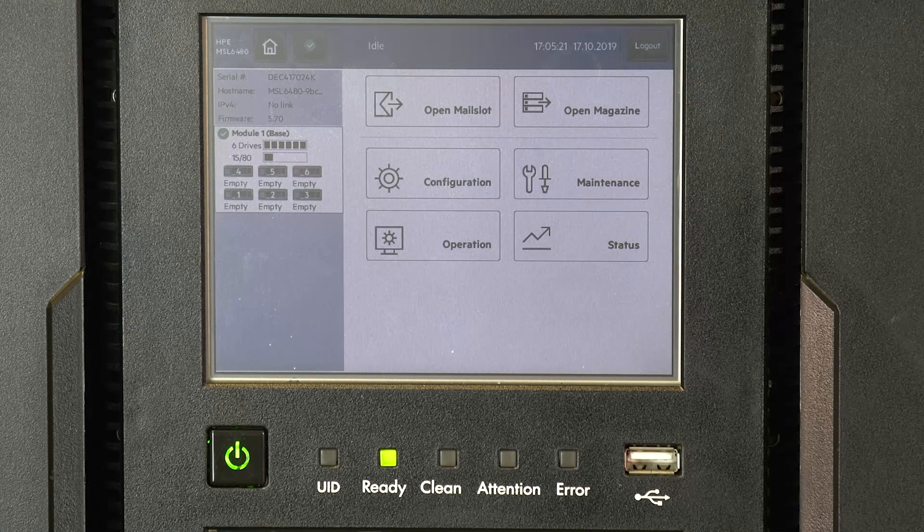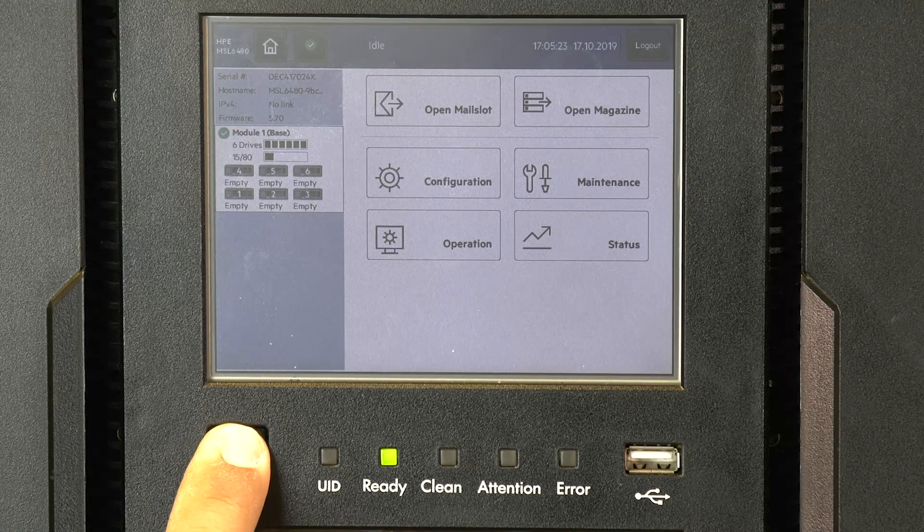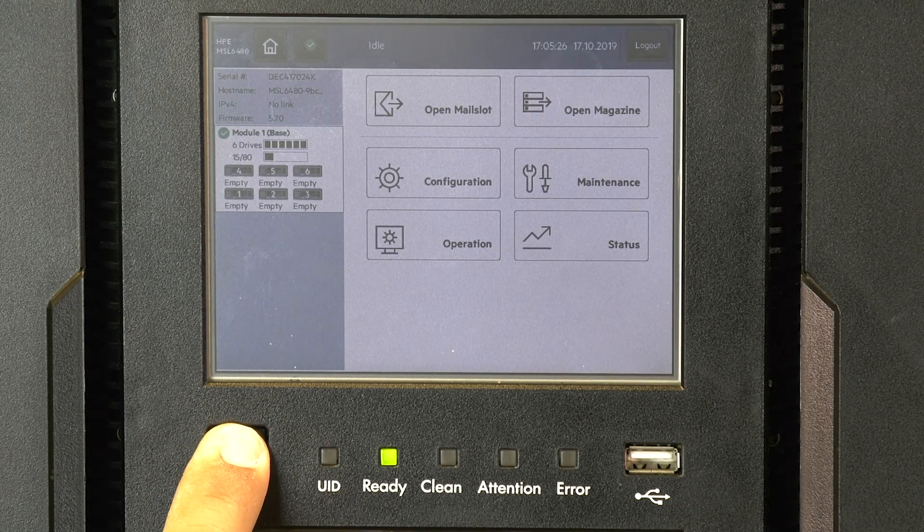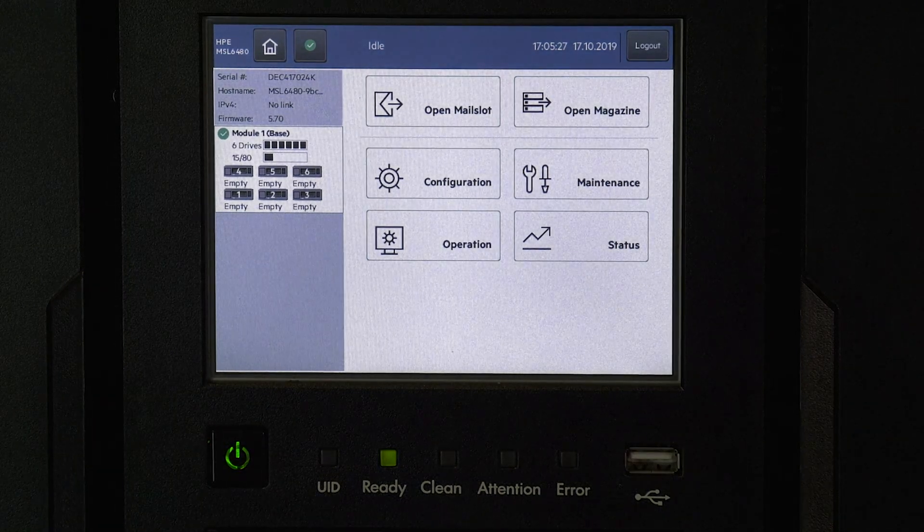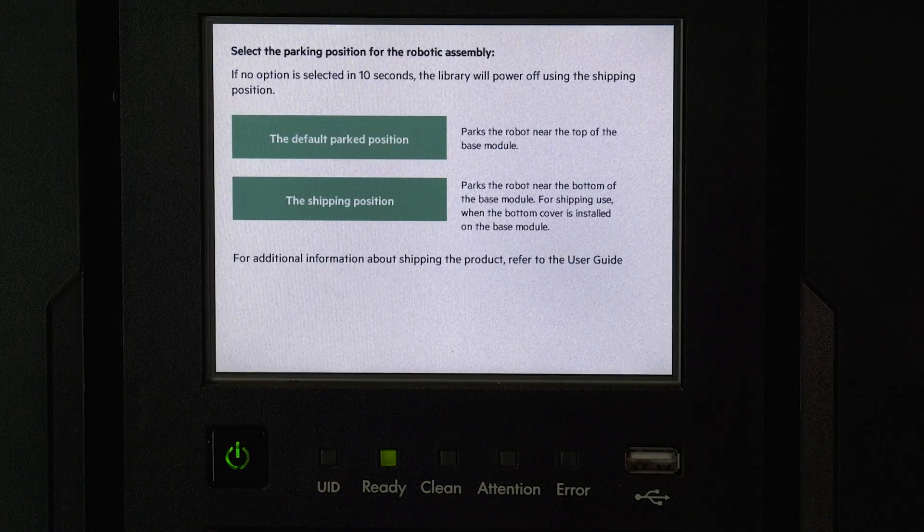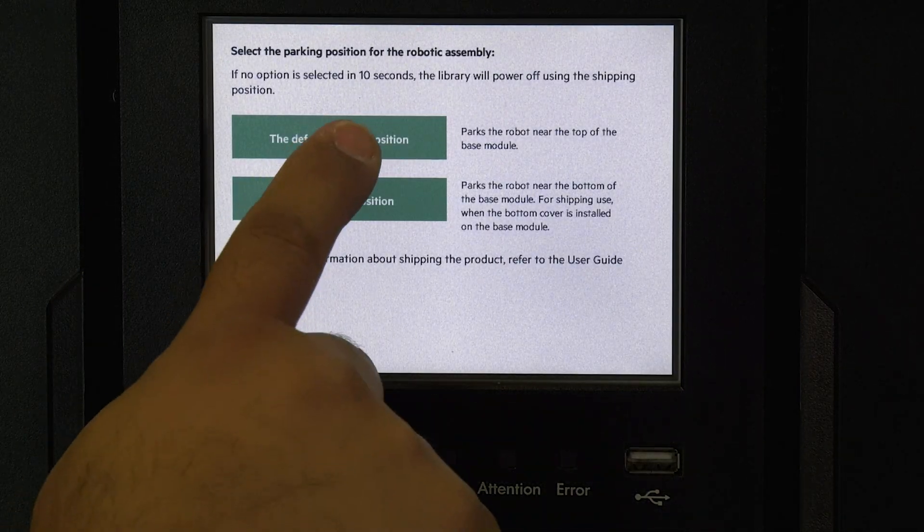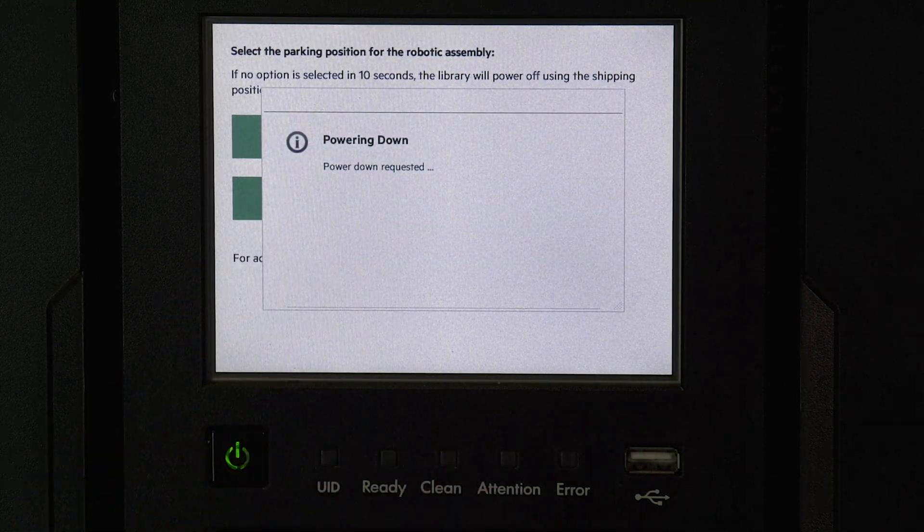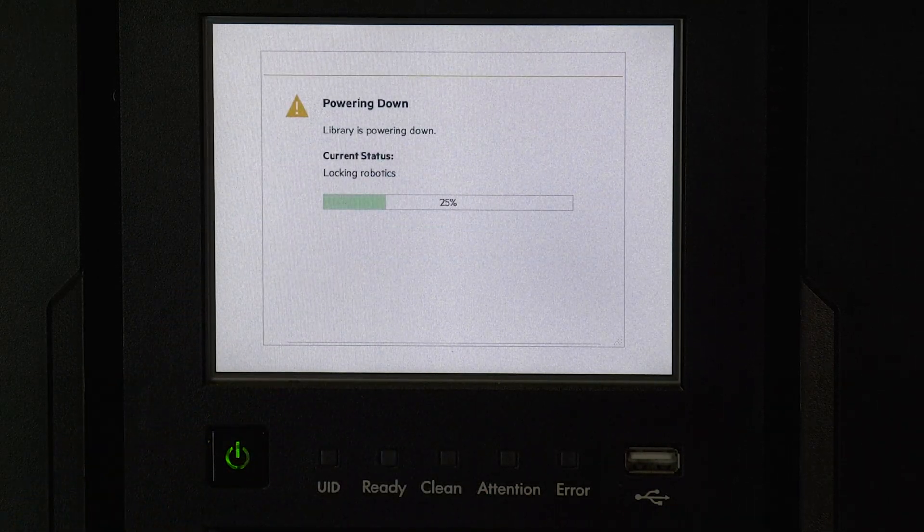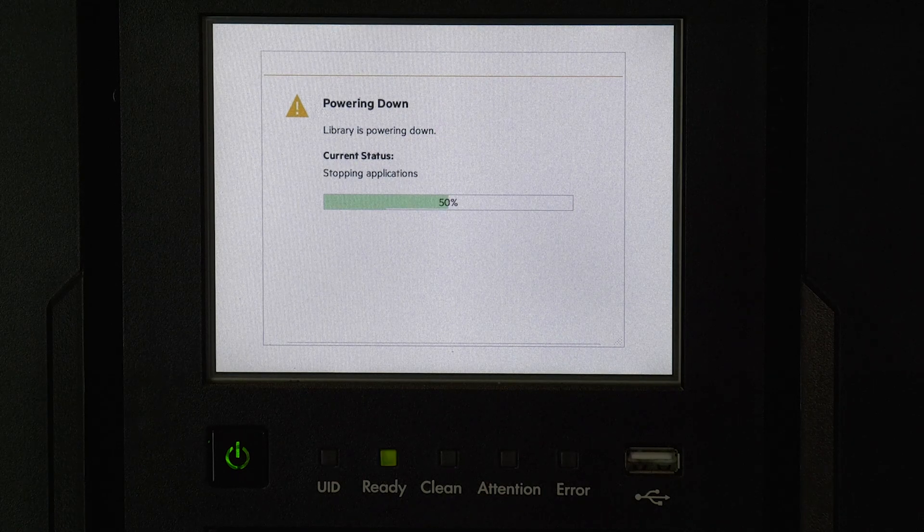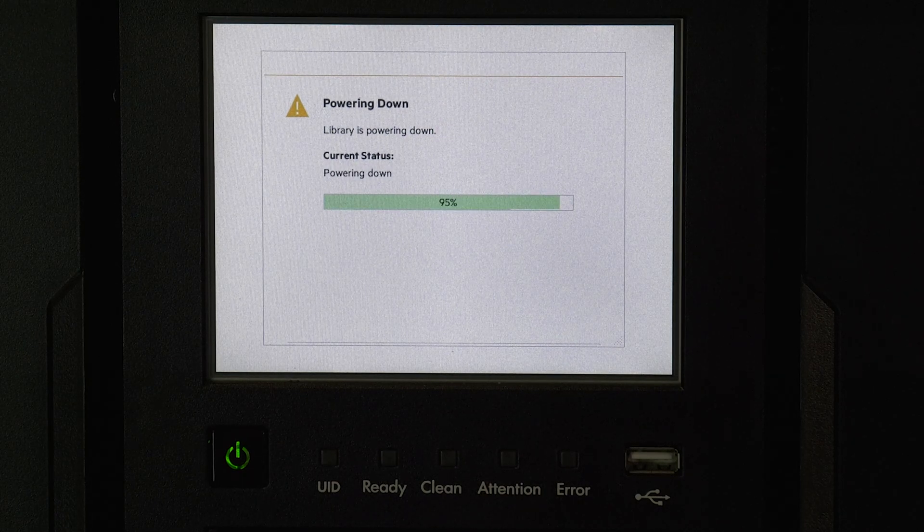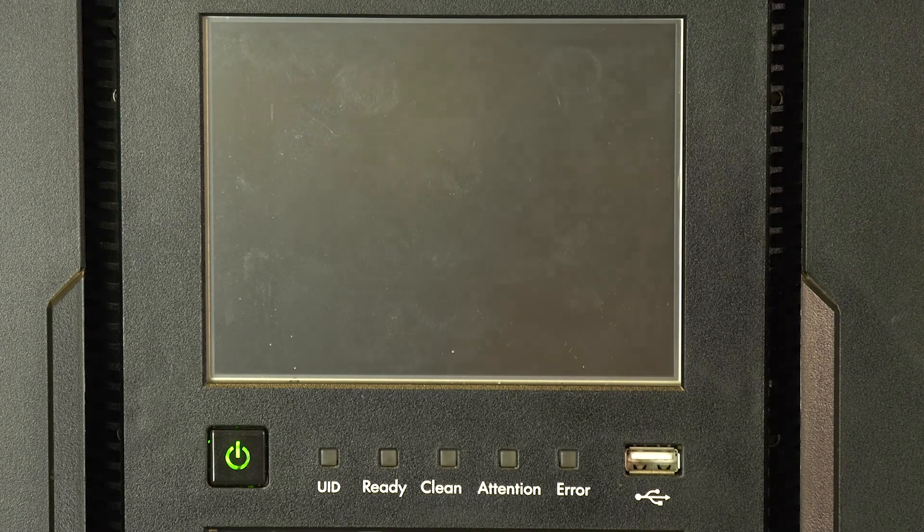Once the configuration is saved, you can power off the library by pressing and holding the power button for approximately 5 seconds and then releasing it. You will be presented with a pop-up asking if you want to put the robot into the default parked position or into the shipping position. Select default parked position and wait for the library to shut down and power itself off. Now you can move to the rear of the library.